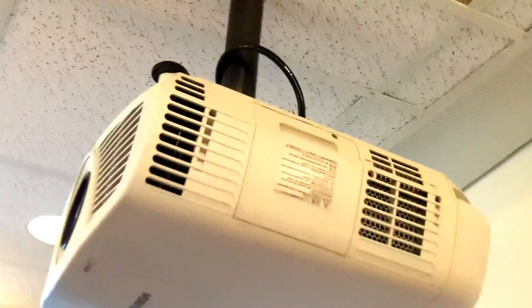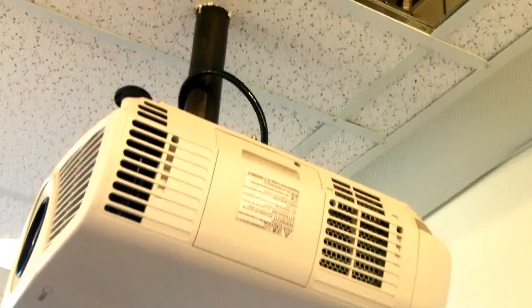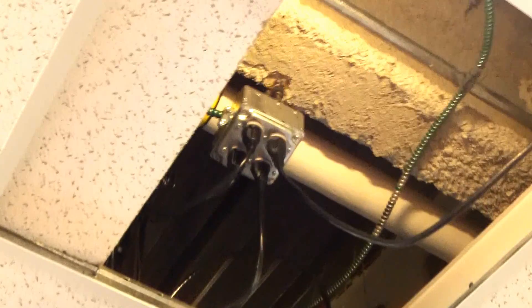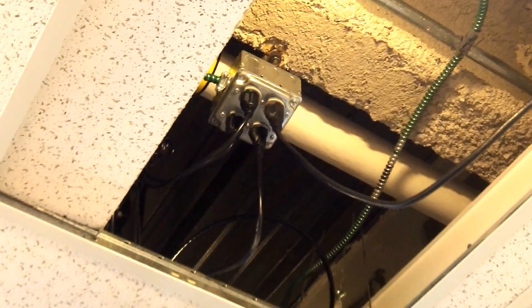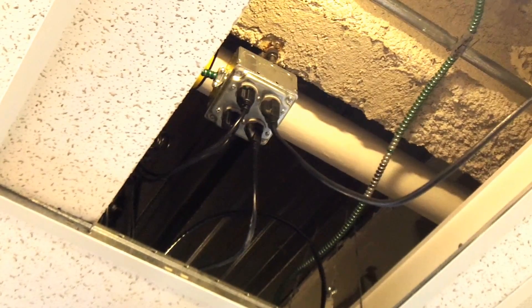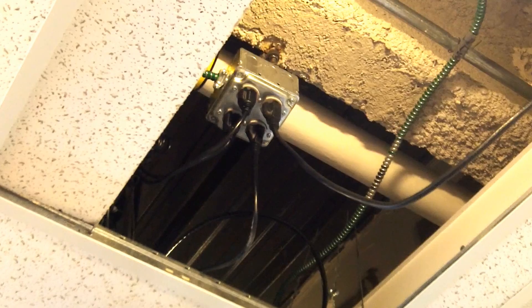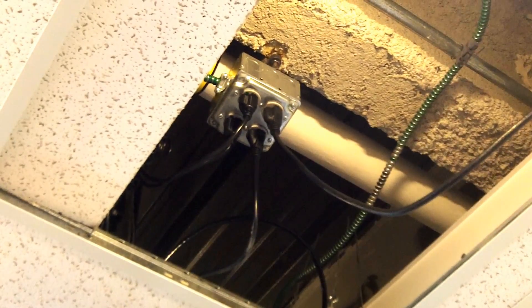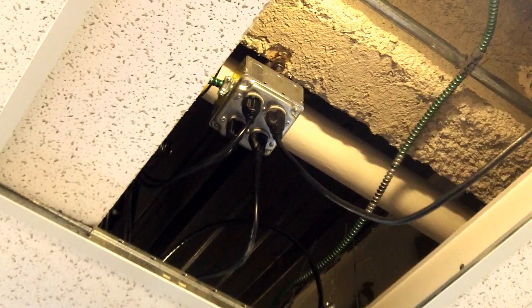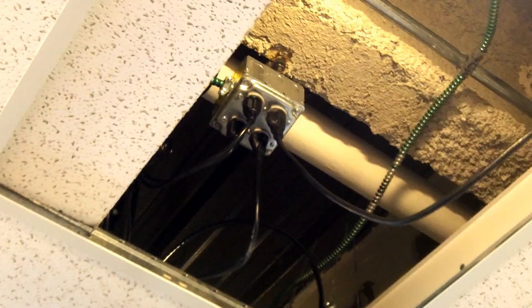But in this application, where we have a projector which is plugged in permanently and the flexible cords for the projector extend up through the ceiling and remain plugged in to those receptacles, this is a violation of 400.8. These flexible cords are not permitted above the suspended ceiling in this application. This is Russell Blank, NEC consultant for EC&M magazine.